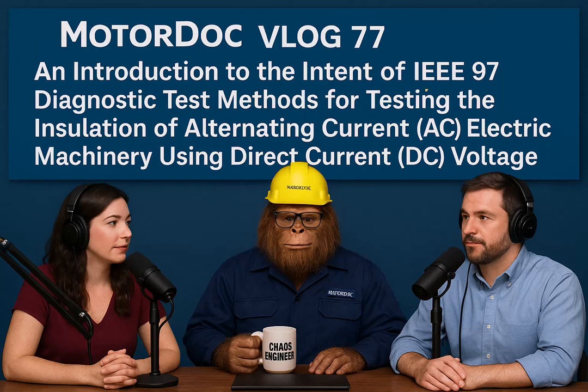Surge capacitors must be isolated before you perform a diagnostic IRP test on the winding itself. Okay. And surge arresters, similar issue. Surge arresters can look dramatic on an IRP, almost like insulation breakdown. The curve might look perfectly normal up to a certain voltage, but then boom, the IR drops dramatically, maybe close to zero, as soon as your test voltage exceeds the arrester's clamping voltage. Well, they need isolating too. Definitely. Isolate them before testing.